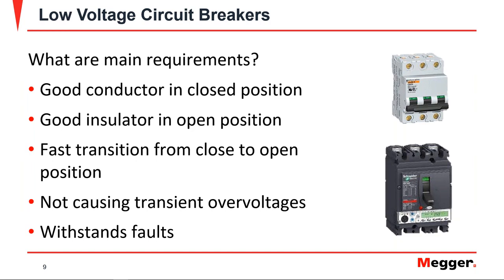When it's open, it has to be a good insulator. It has to be able to transition fast enough from closed to open or vice versa, especially on the open operation, or the trip operation as we commonly call it. While performing those operations, it's important that it doesn't cause any transient voltages, and that it should be able to withstand faults.